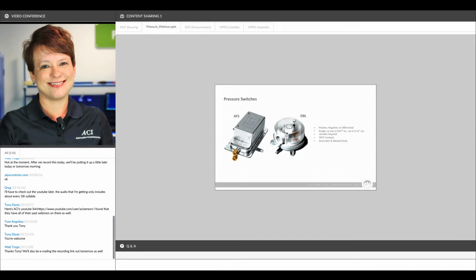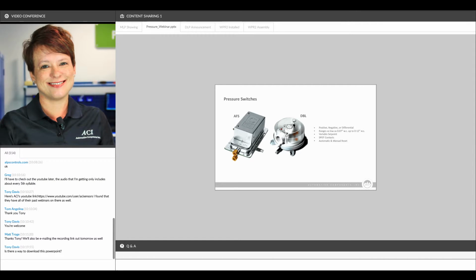We have pressure switches available for you. These are all going to be for dry air or inert gas. The lowest pressure ranges are plus or minus 0.07 inches of water column, up to 12 inches of water column. Variable set points are available. All of them are going to have single pole, double throw relays. And you can get both manual and automatic resets.